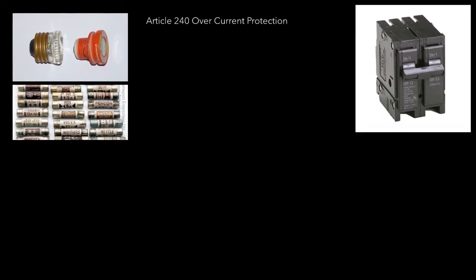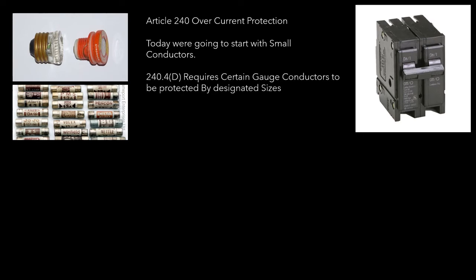We're in Article 240, and that's gonna be our overcurrent protection article in the NEC. Today we're gonna be dealing with small conductors — so this is when you're dealing with small conductors: 14, 12, and 10 gauge. Section 240.4(D) requires certain gauge conductors to be protected by designated overcurrent device sizes, and we're gonna talk about that now.